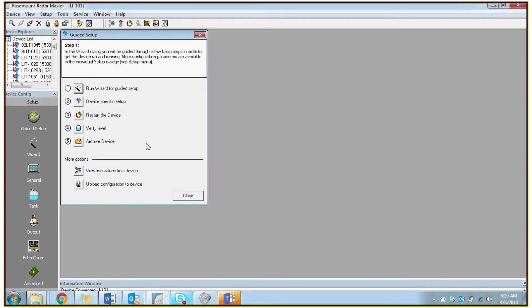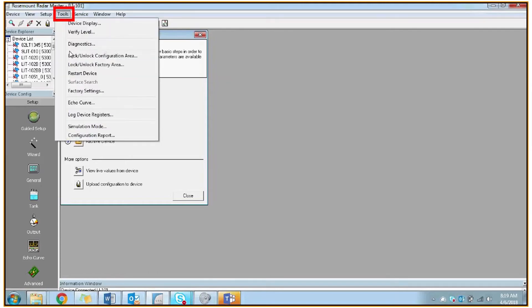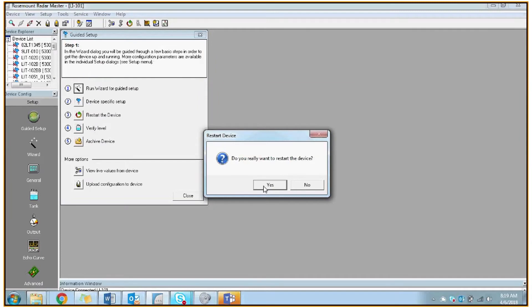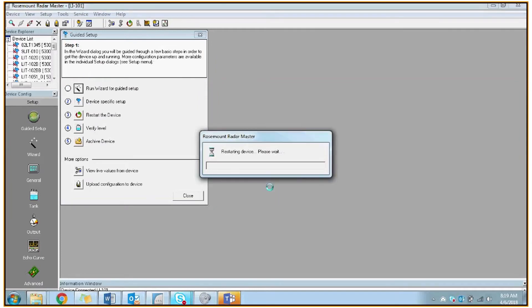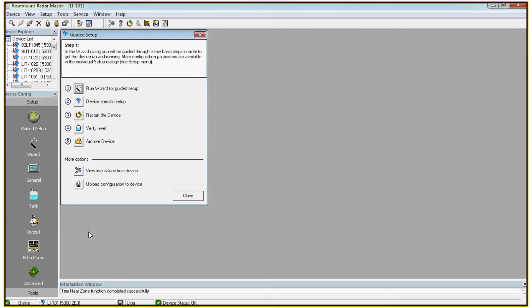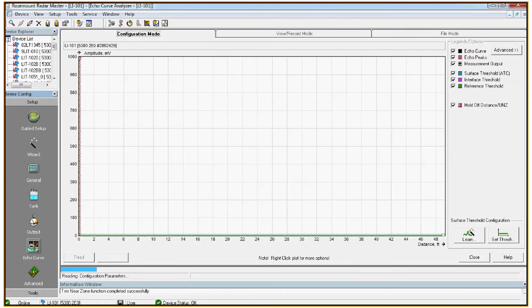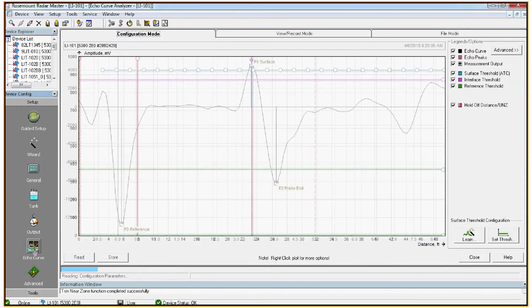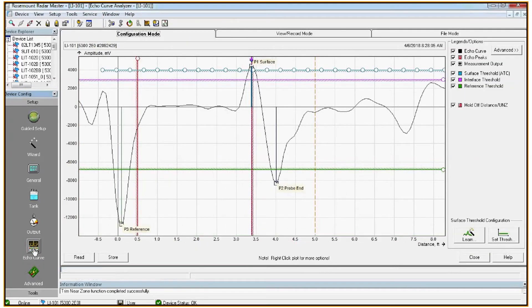Now that we have all the main configuration parameters stored, we want to make sure we go into tools and do a restart. Next we'll want to open an echo curve. So in the bottom left side of the screen, click the echo curve button. It'll take a few moments to load an echo curve. The echo curve is a visual representation of what you'll see kind of inside the vessel. We won't get into too much detail about the filtering and how to read these in this video. We'll have another video on troubleshooting.